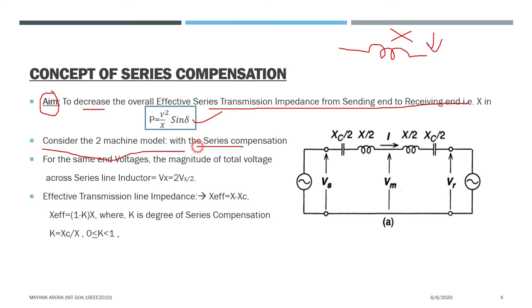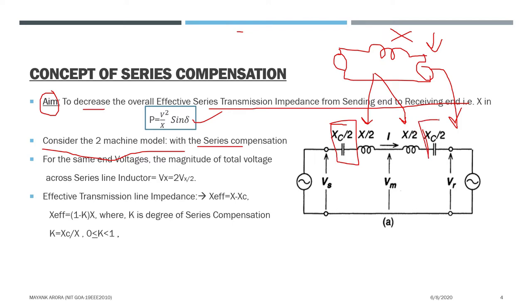We will consider a two-machine model with a series impedance. When we consider the uncompensated transmission line, we represent this system with X, VS, and VR. With series compensation, I will divide the transmission line impedance into two halves — X/2 and X/2 — and add series compensation at each half. This way, if one part becomes a short circuit, the other part can handle that short circuit current.